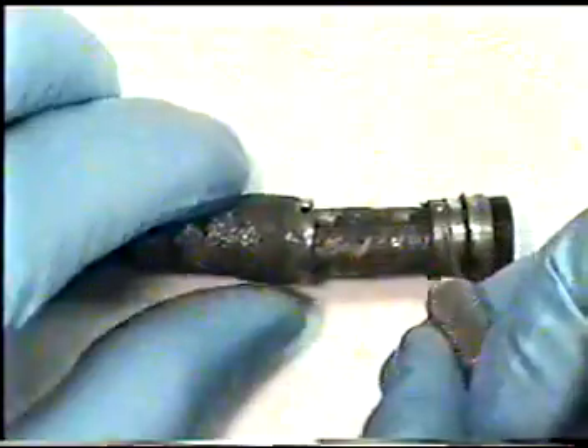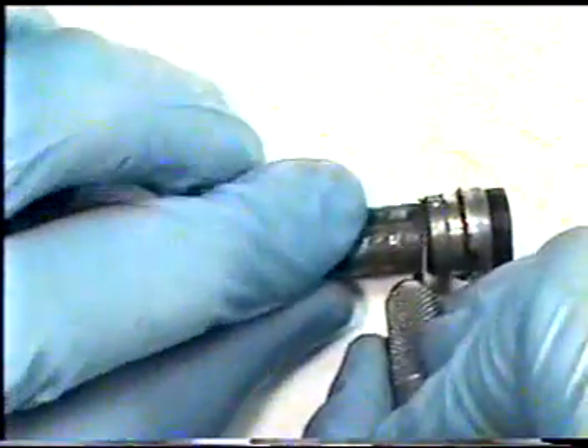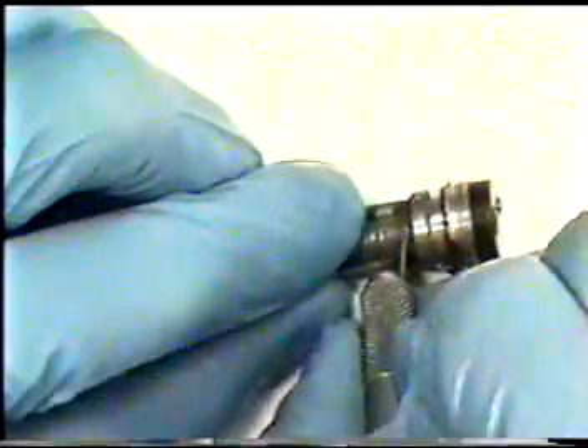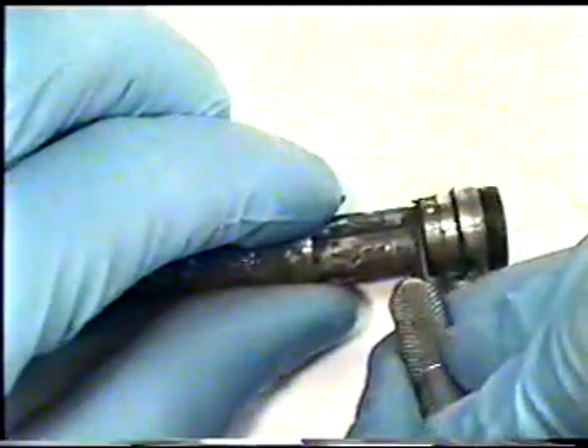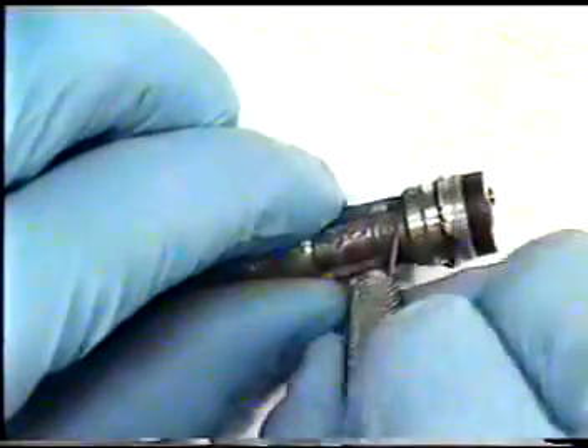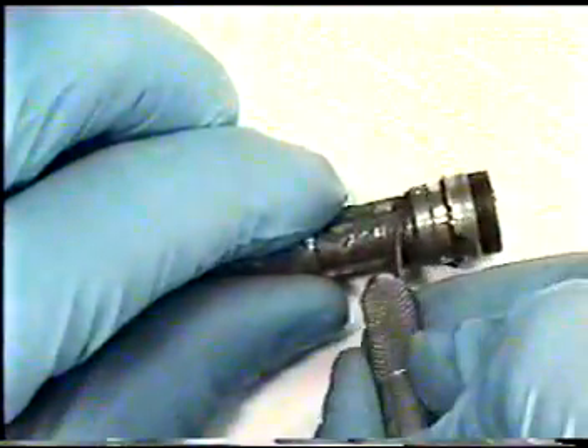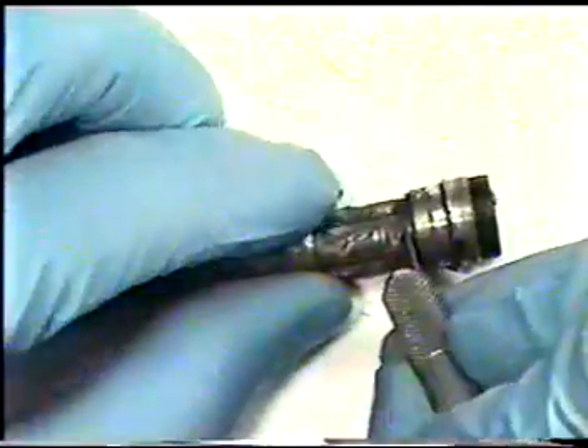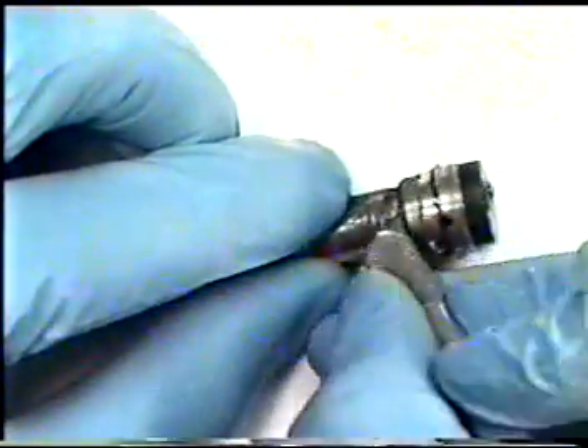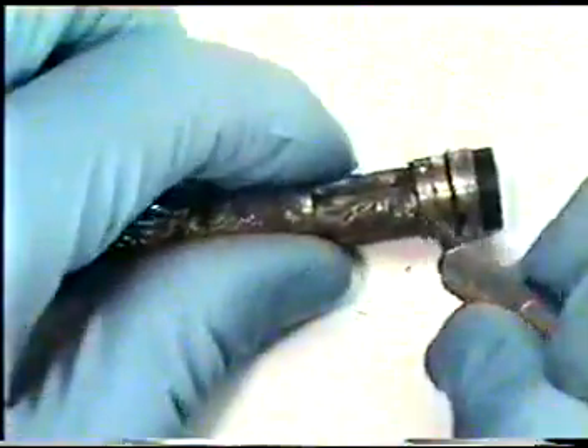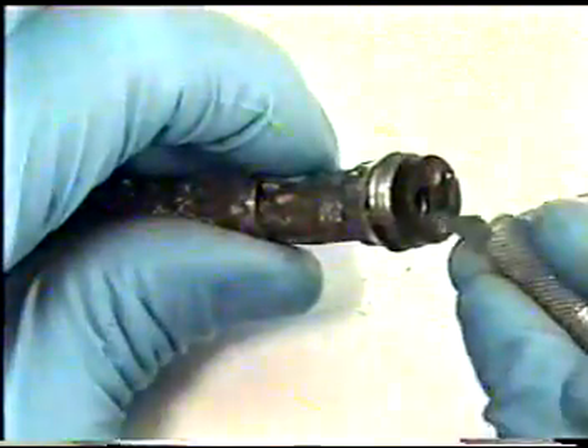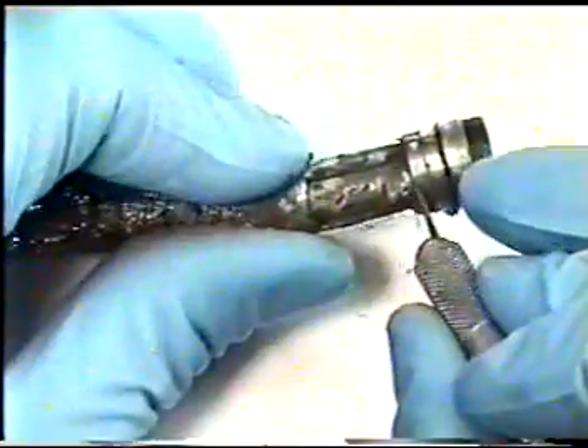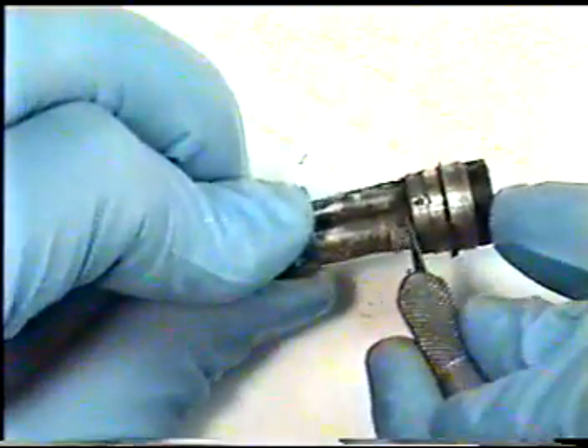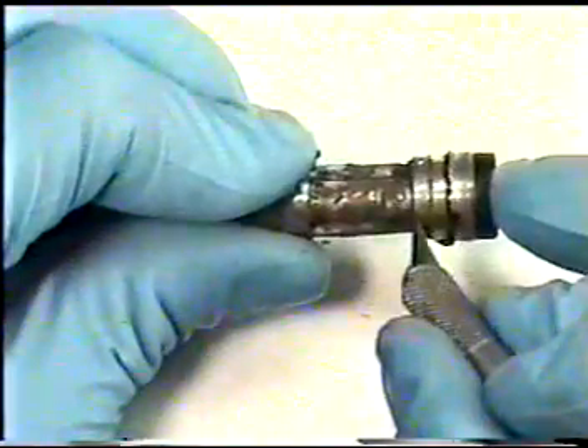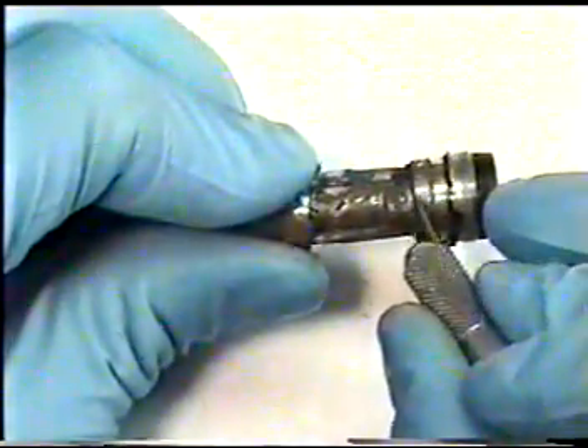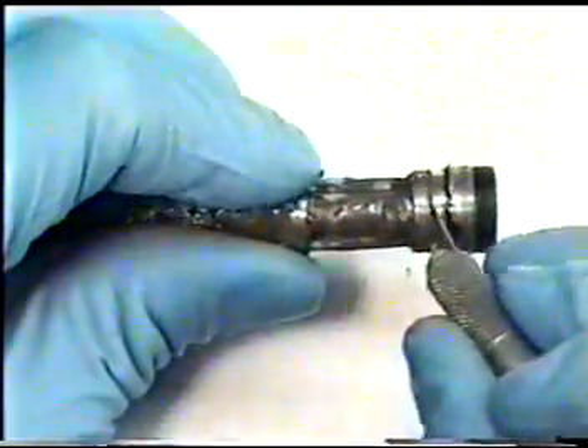Using a very sharp X-Acto blade knife, carefully remove biopsy channel as previously shown in biopsy channel replacement. Always be sure to locate your biopsy channel to make sure that you are, in fact, cutting away at the biopsy channel and not your light guide bundles at this time, or your other channels such as air, water, or CCD chip or image bundle.